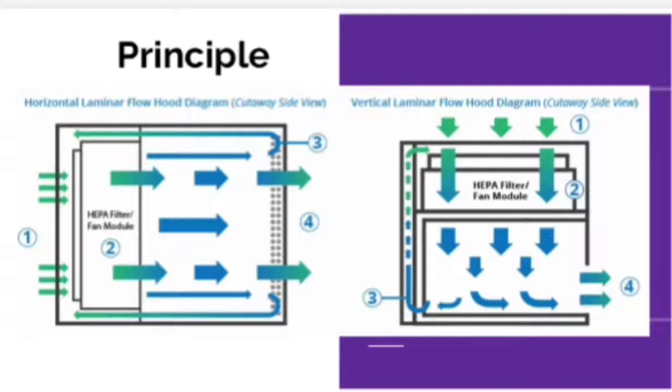The air first passes through the filter pad or pre-filter that allows a streamlined flow of air into the cabinet. Next, the blower or fan directs the air towards the HEPA filters. The HEPA filters then trap the bacteria, fungi and other particulate materials so that the air moving out of it is particulate-free air.